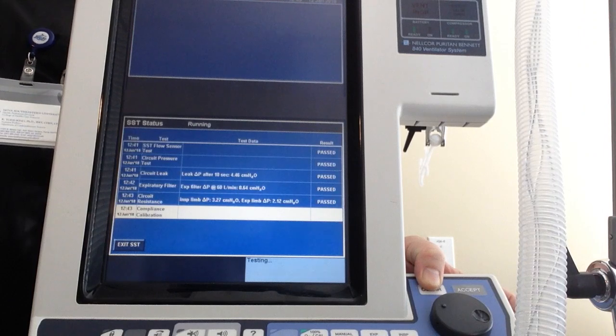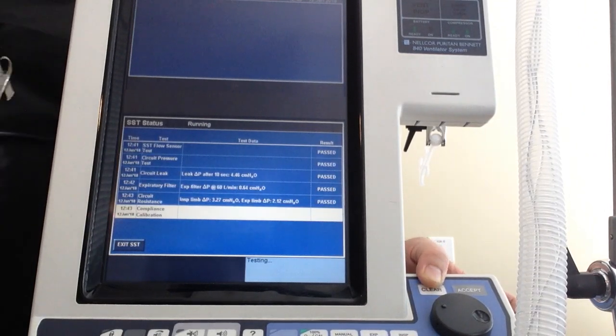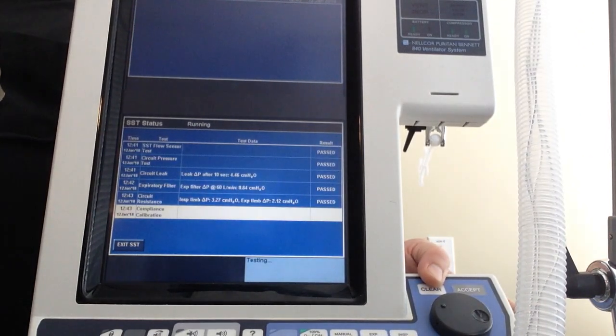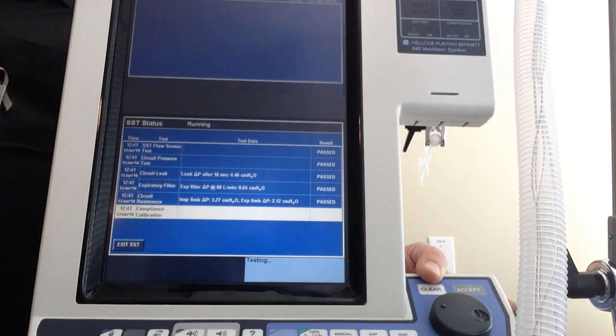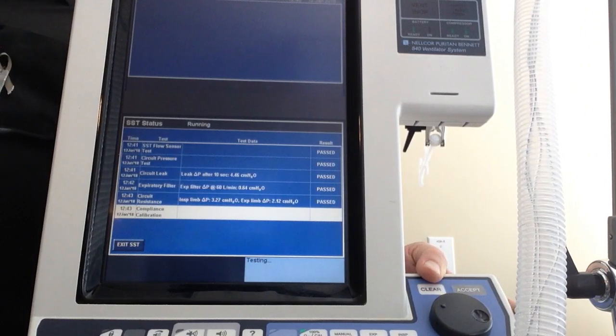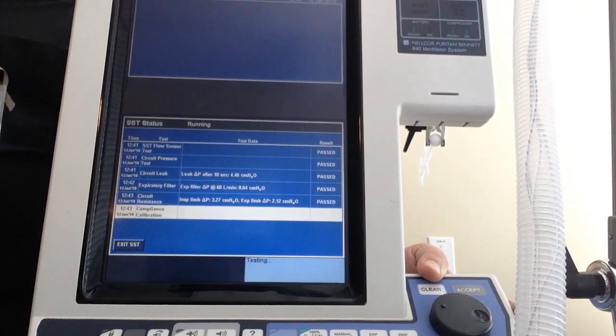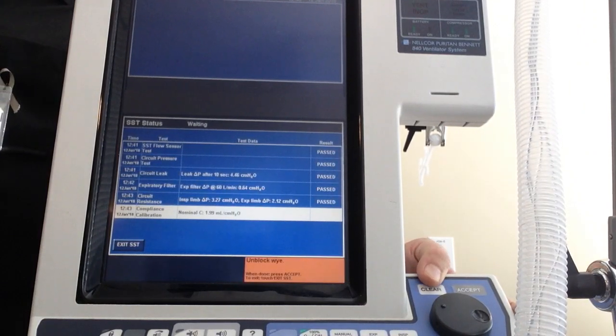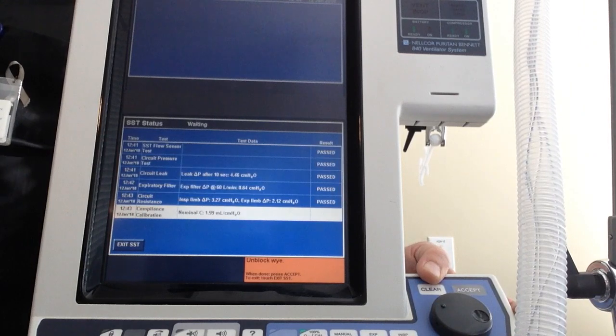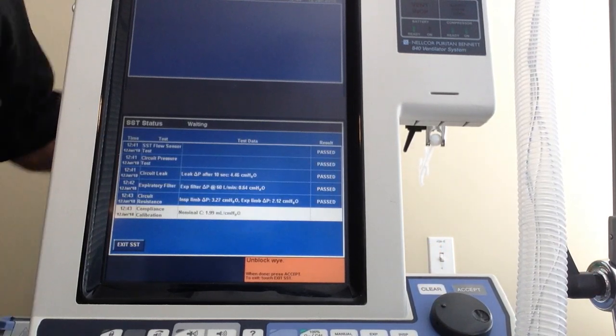Now it's testing for tubing compliance. Tubing compliance is how much stretch your ventilator circuit has. If you do not compensate for the stretch, you will be giving your patient less volume than what you think you will be giving them. So if you have a 10 cc stretch in the tubing and the patient is supposed to be receiving 500 cc's or 500 milliliters, then the patient would only be getting 490. By the machine knowing how much stretch is in the tubing, it adds that volume in automatically.